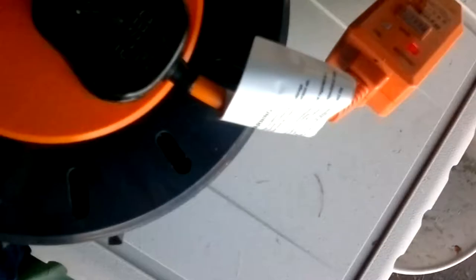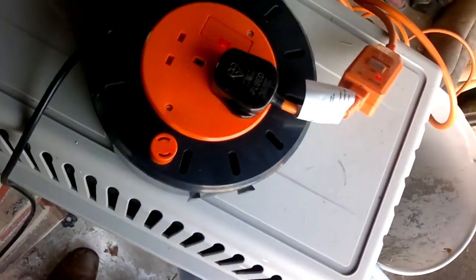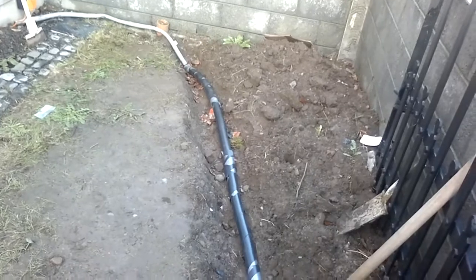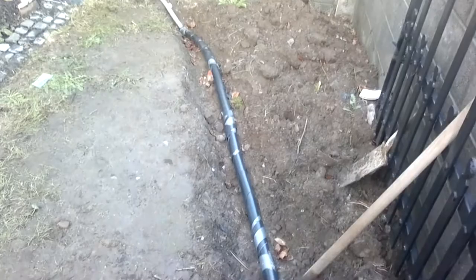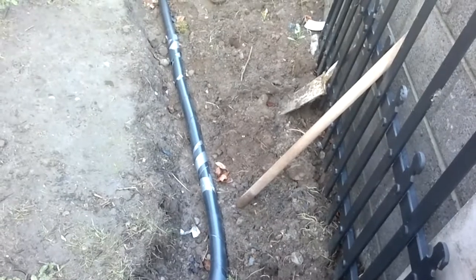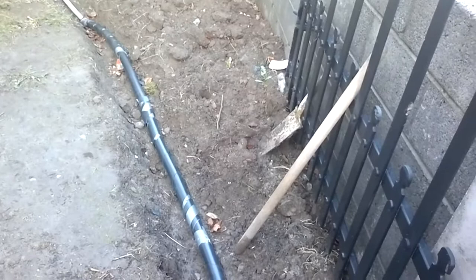I'm testing this thing while I'm laying it just to see what kind of heat's coming out through the different ducting. Here's the entire thing laid and traced - a trace laid with double sheath and damp proofing. Power's onto it, there's no smoking or melting. We'll see how it runs over the next few days. Trace heating installed.